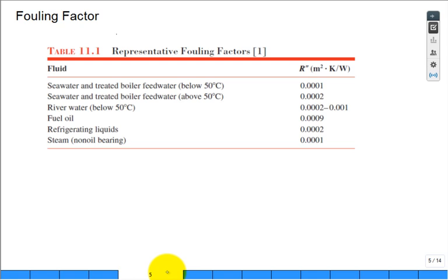Well, not only can you have the fluids flowing through and you have the convective resistance, if you wait long enough, some of those fluids will actually deposit some stuff on the sides which will inhibit or degrade the heat transfer. It'll be an additional resistance. It's called fouling of that heat exchanger. So you would have the convective, then some fouling, then some conductive, then maybe another fouling, and then convective out to the fluid again, T infinity here, T hot, T cold.